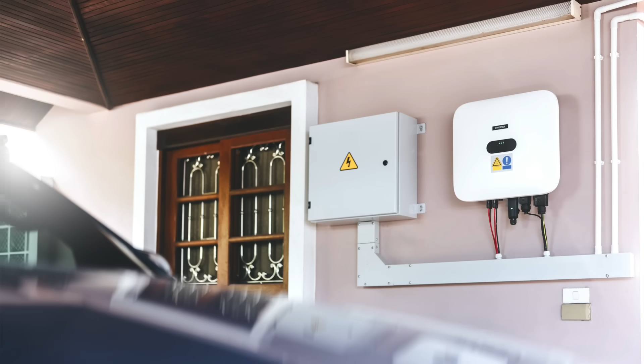The IET spells out the necessary earthing advice in its advisory. Another key aspect with battery systems is their performance under fault conditions. The organisation warns that many inverters won't deliver the current needed to trip the protective devices, so managing protection for faults requires much more diligence. The updated guide costs £55 for non-members, and I've put a download link in the show notes.